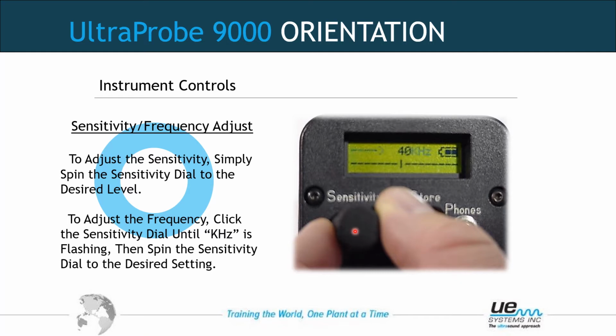If we push the sensitivity button in, click it, kilohertz will begin to flash, KHz. It is flashing right now, meaning I can adjust the frequency anywhere between 20 and 100 kilohertz by turning the sensitivity dial. Once that frequency is set to where you want it, as it is here, you would push the sensitivity button and it would just jump back to the sensitivity area and decibel area where you can adjust sensitivity. The two positions on the screen are sensitivity and decibel and the frequency position. It toggles between the two by pushing the sensitivity knob in.